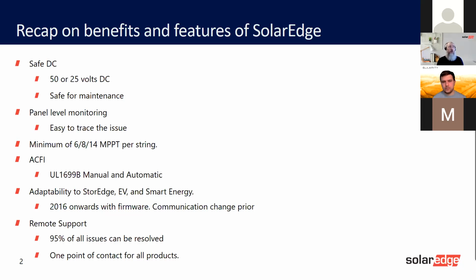Having arc fault circuit interrupter or arc detection that you see other inverters have, other manufacturers have, is great, but you must have a way of controlling that current. And the only way is SolarEdge, this optimizer controls the current and reduces it from 14 to 15 amps, which we tend to run, to 200 to 300 milliamps, as I said.